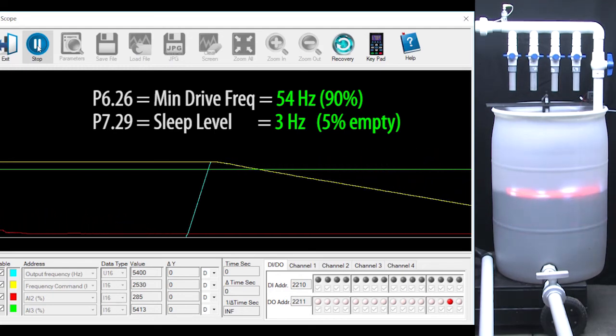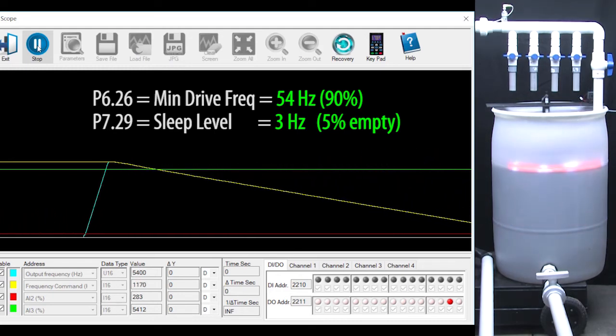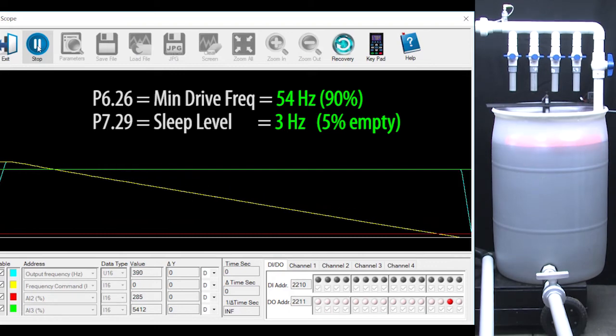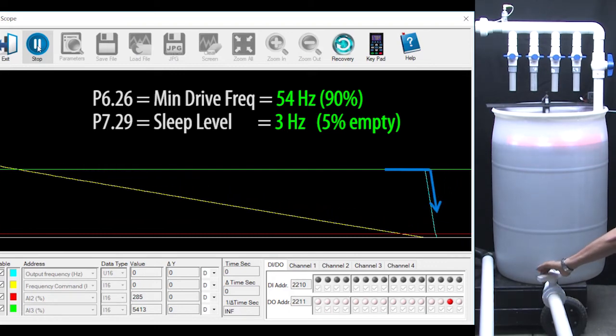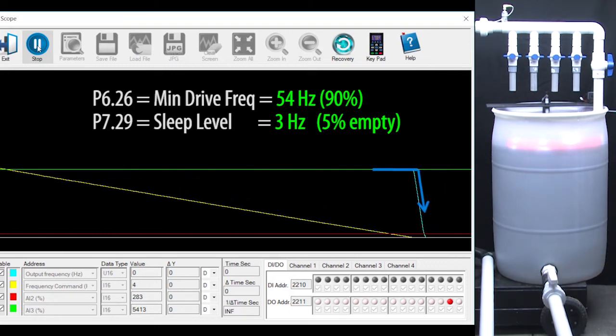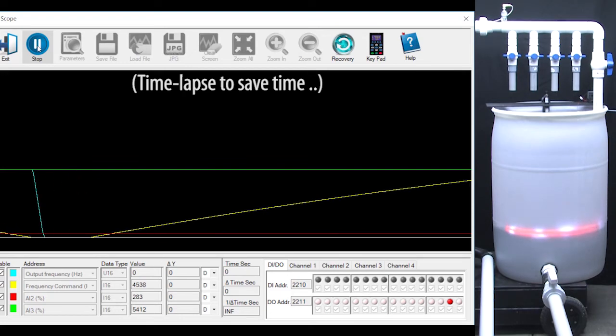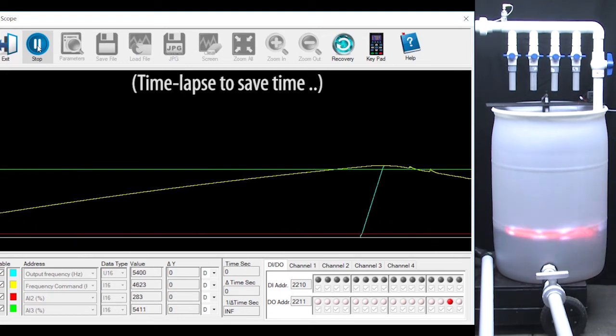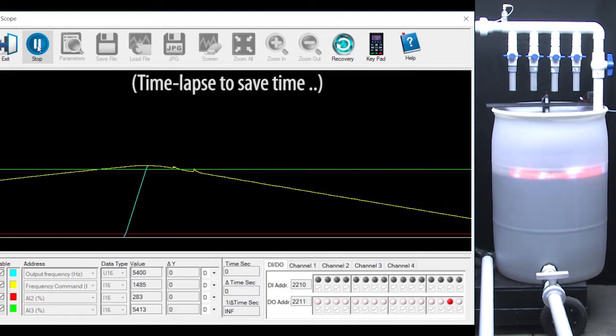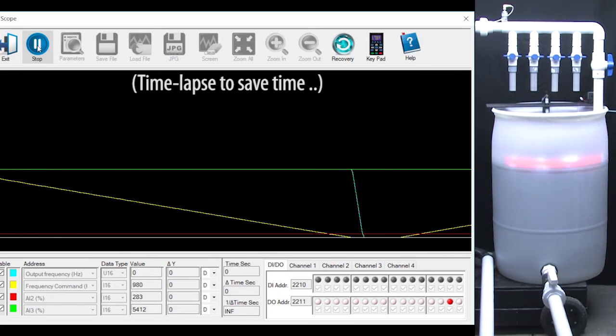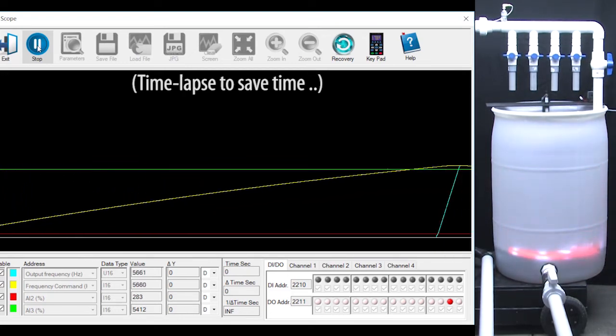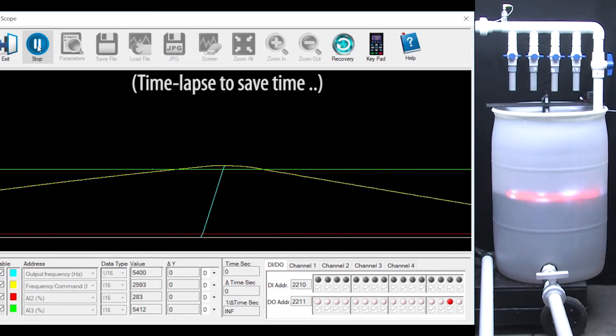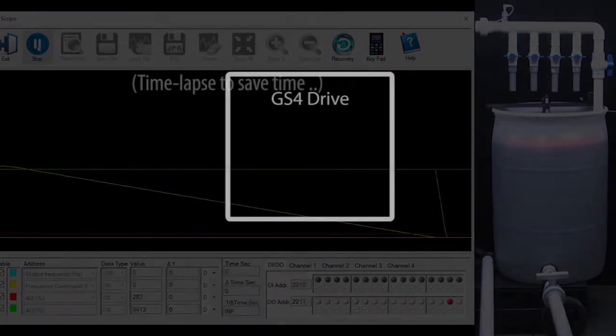When the sensor hits the new sleep level of 3 Hz, the drive shuts off after the 2 second delay. So now the motor is filling the tank quickly independent of the sensor value and is filling to whatever level we specify. Perfect.